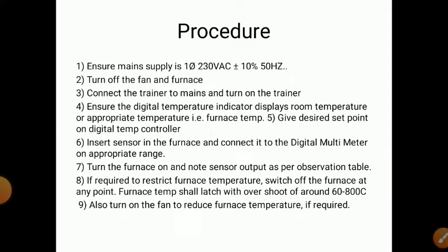For the procedure: ensure main supply is 230V AC ±10% 50Hz. Turn off the fan and furnace. Connect the trainer to mains and turn it on. Ensure the digital temperature indicator displays room temperature or furnace temperature. Set the desired set point on the digital temperature controller.